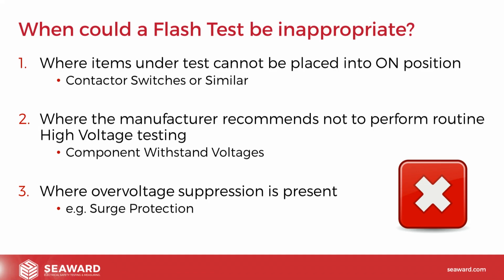I'm sure many of you will be familiar with surge protected extension leads. The purpose of those extension leads is that if they spot an overvoltage, they effectively short the live conductors to earth, to send all of the excessive voltage away back down through the earth cable, keeping the product it's protecting nice and safe. Now, when we apply a high voltage test, like a flash test, where we are testing at 1,000 volts plus, that will always be seen as a potential hazard to these devices.